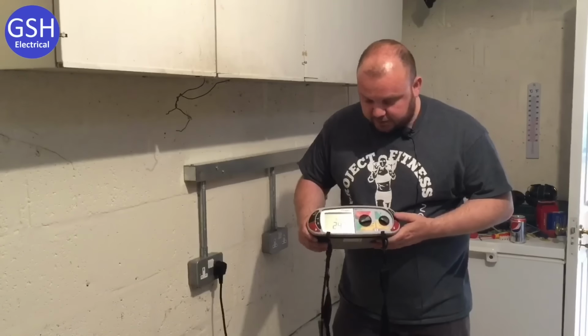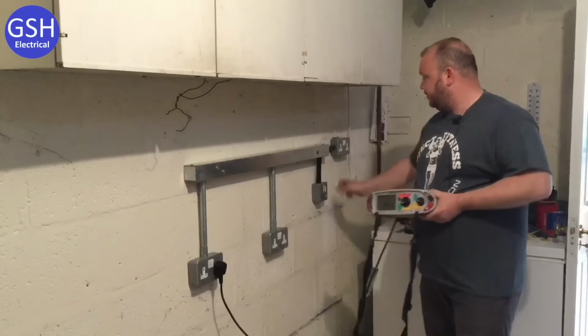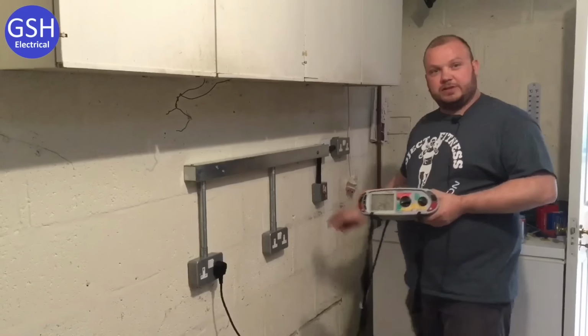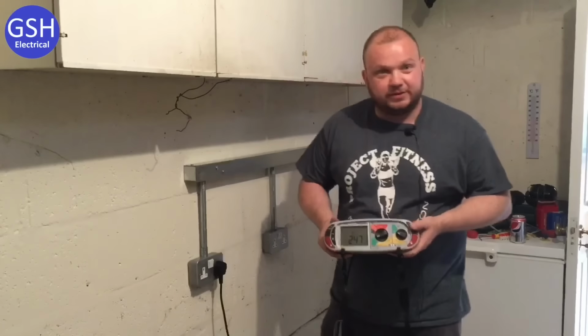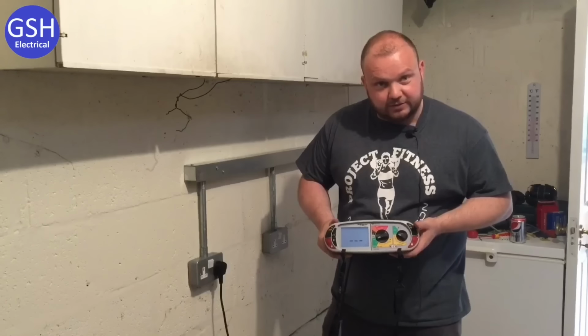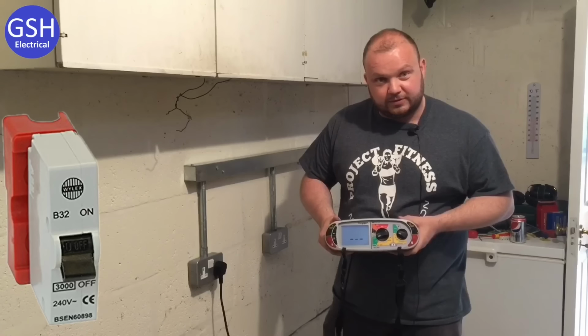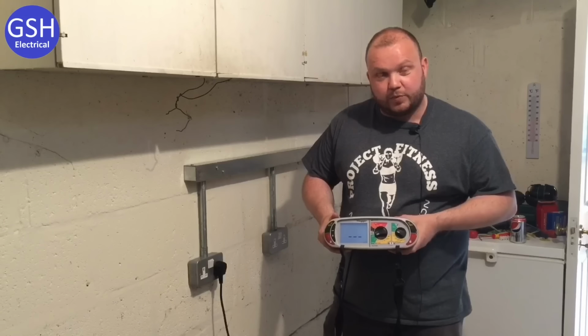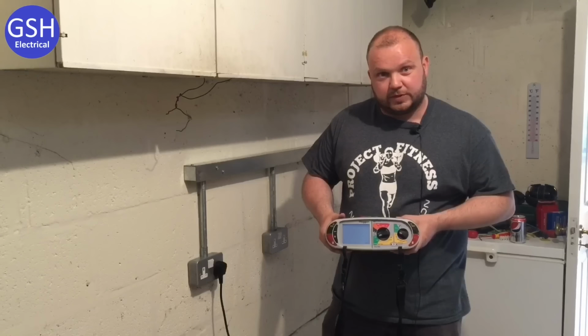Okay, why is that? Why are you using 3 lead low? I'm using 3 lead low because we've got an RCD in. Okay, brilliant. So we need to do it that way. This is going to take a little while. Okay. What's the maximum value this can be for a 32 amp type B circuit breaker? This is 1.1 ohms. Okay, so we hope this reading is lower than 1.1 ohms, do you agree? Yes, I agree. And it's still taking an eternity.